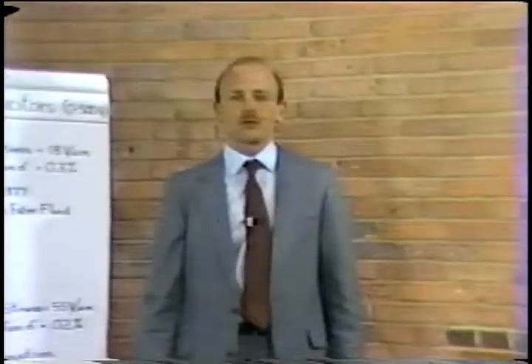This takes place in approximately 10 microseconds and involves an almost imperceptible reduction in the capacitor voltage and charge stored on the electrodes. An electron microscope picture of a piece of film containing a clearing is shown here. In the center, we see the defect area, which is surrounded by a demetallized area. And finally, surrounding that is the aluminum electrode. This clearing, or self-healing property, allows us to reliably operate very thin polypropylene films at extremely high stresses. We can easily demonstrate the clearing process in metallized film.